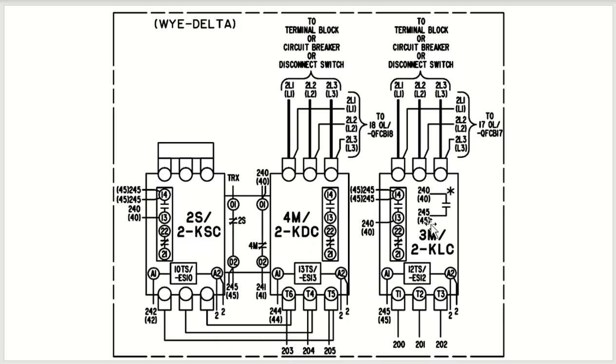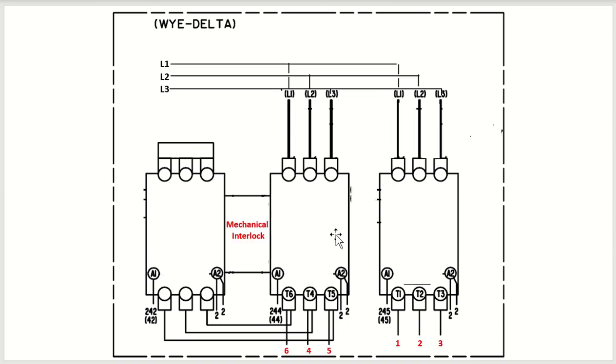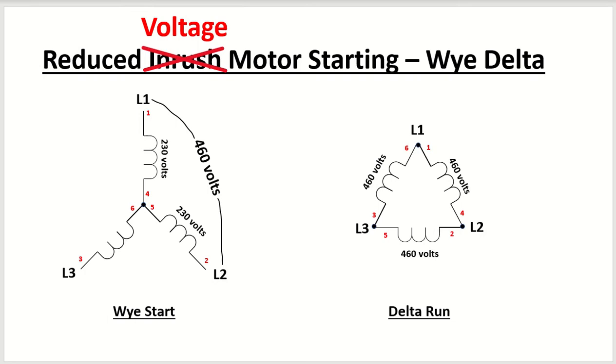A typical Y delta starter package would look something like this. There's three contactors. I know there's a lot here that's kind of confusing. This is from a York chiller diagram. I kind of whited out most of the stuff to make it look a little bit easier to understand, I hope. You see up here you've got your three-phase power coming in. It feeds the top of these two contactors, and this contactor here is called a shorting contactor, and you'll see how that works. Let's put some numbers to the motor leads here in our configuration.